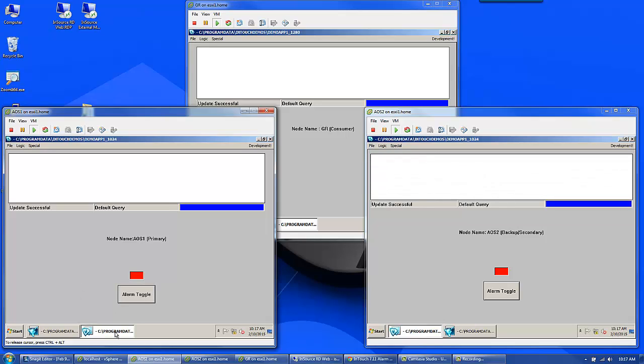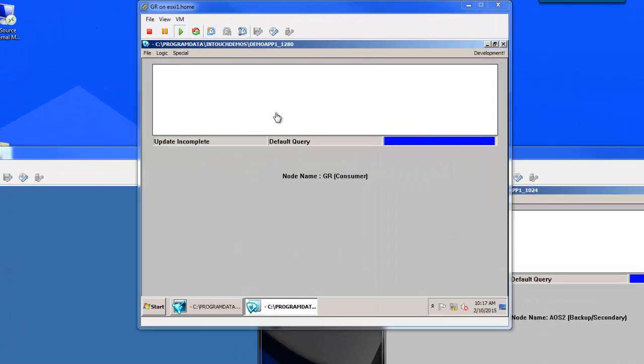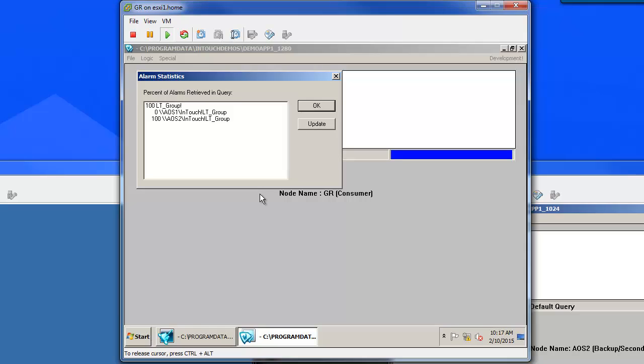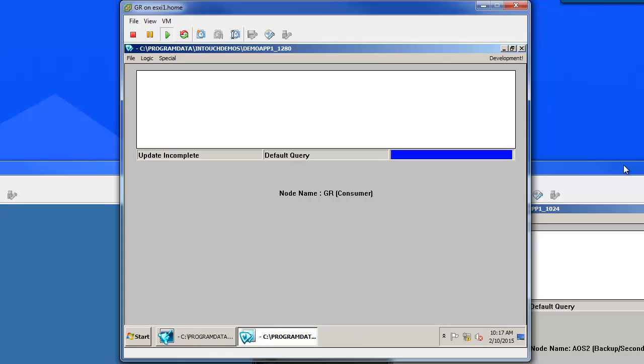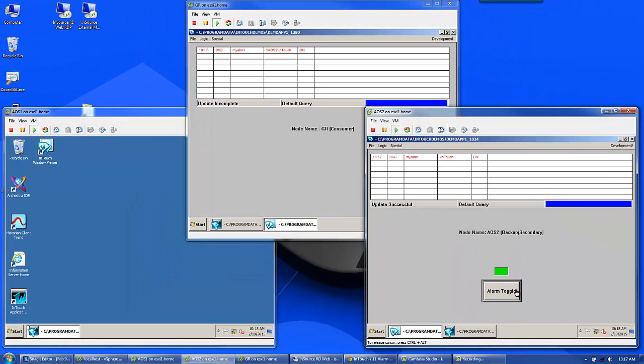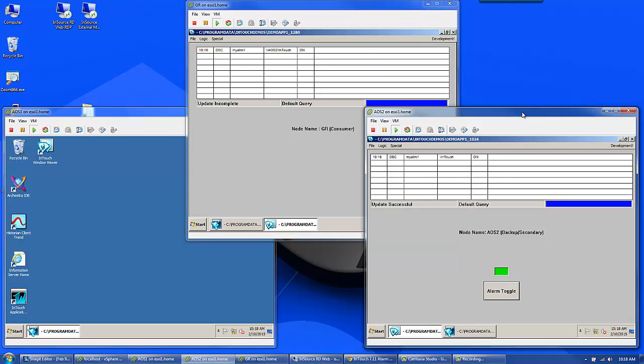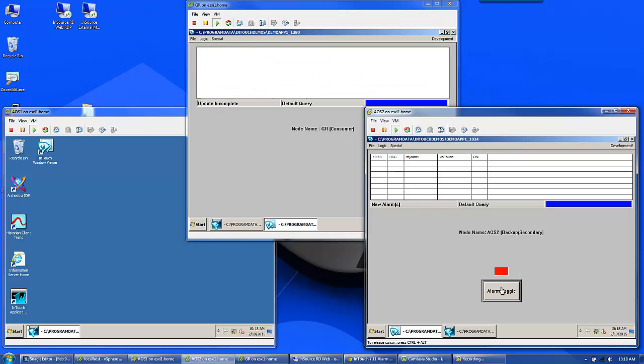Now we'll go through a scenario of losing one. I'm going to simulate a failure. You can see up here at the client — the consumer — we've indicated that we can't see all of our alarms. We've lost AOS1. That's okay. I'll go generate the alarm again on AOS2. You'll see that I'm still getting my alarms on the consumer node, and I can acknowledge from again at any node. We'll go ahead and clear this alarm.